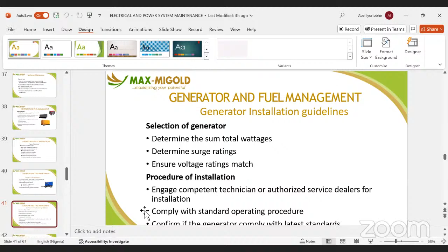You need to use the exact size of cable to install your generator. Don't say you don't have money and go use a lower rating, because if you do that, sooner or later your cable will melt. The money you don't want to spend, you'll end up spending because heat passes through your cable. If the heat is too much, the cable will melt, the insulation will break down, and there will be a short circuit. If care is not taken, it will damage your generator. When three lines are bridged together, it will affect your alternator, and you end up losing everything - whereas we wanted to save money by compromising standard. Ensure you practice according to industry standard, SOP.